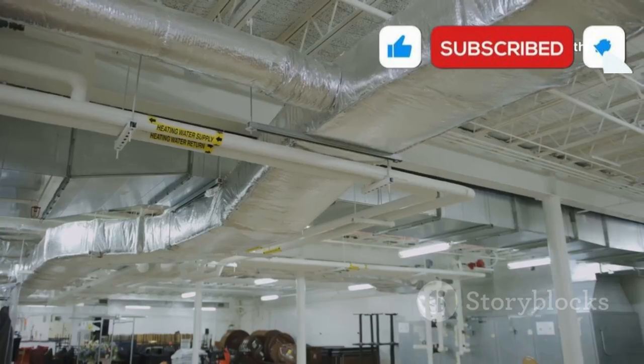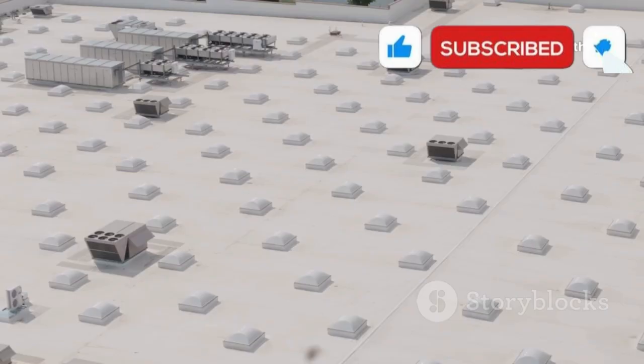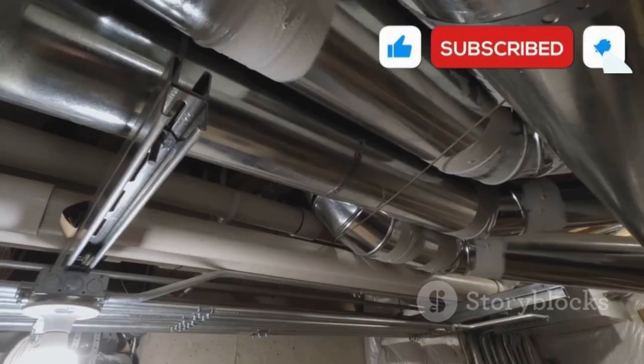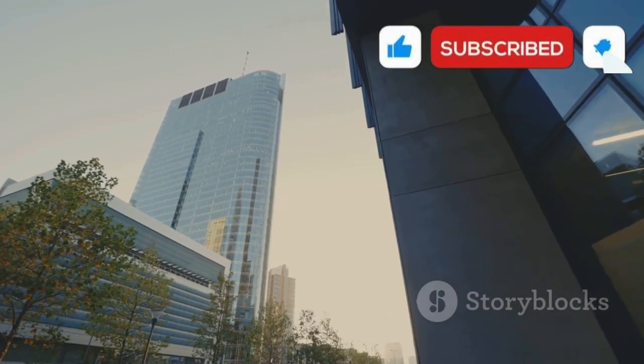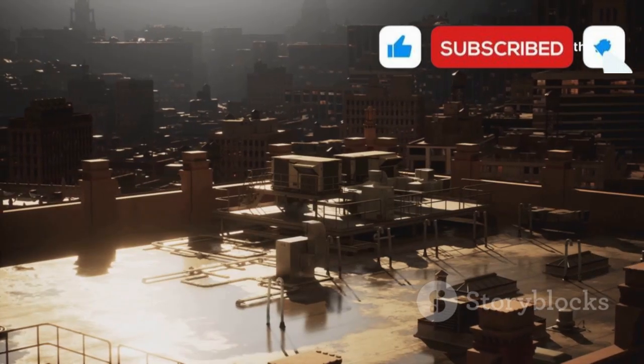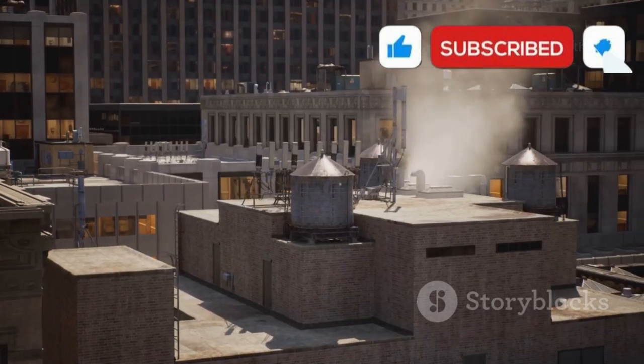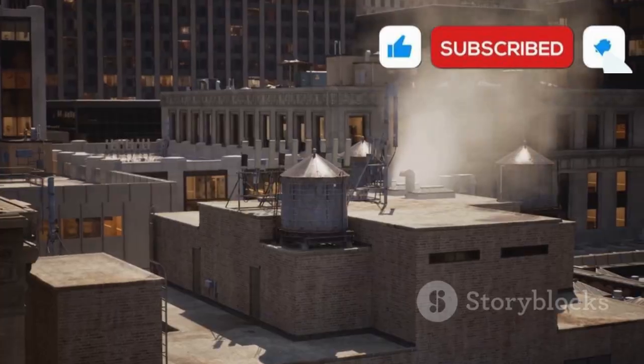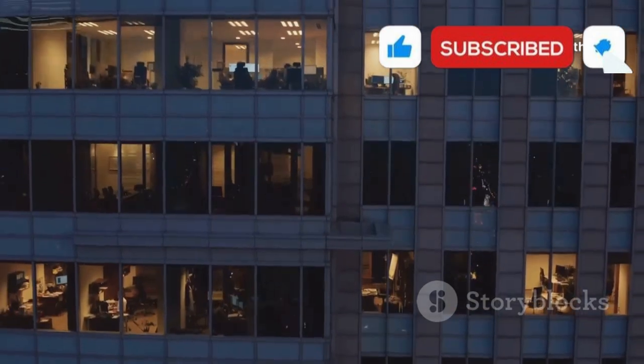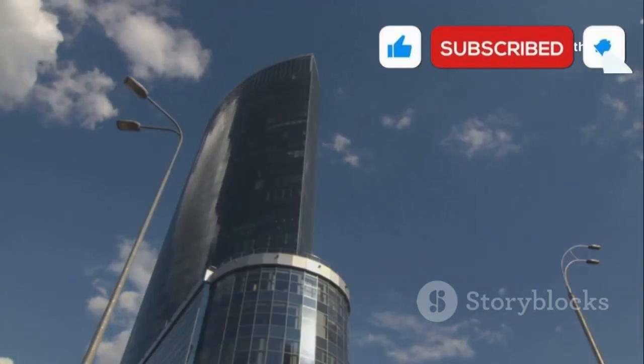Ductwork distributes the cool air throughout the building, while return ducts bring warm air back for recooling. This creates a continuous, efficient cycle of cooling and air movement. Engineers carefully design pipes and ducts to ensure every area gets enough cool air. The system is precisely controlled to maintain comfort and save energy. It's a silent, orchestrated dance of water and air, happening above ceilings and below floors. Without this system, skyscrapers would quickly become ovens. The movement of water and air is the lifeblood of skyscraper cooling. It's all about delivering comfort to every corner, no matter how high. Next, let's see where all this powerful machinery is hidden.